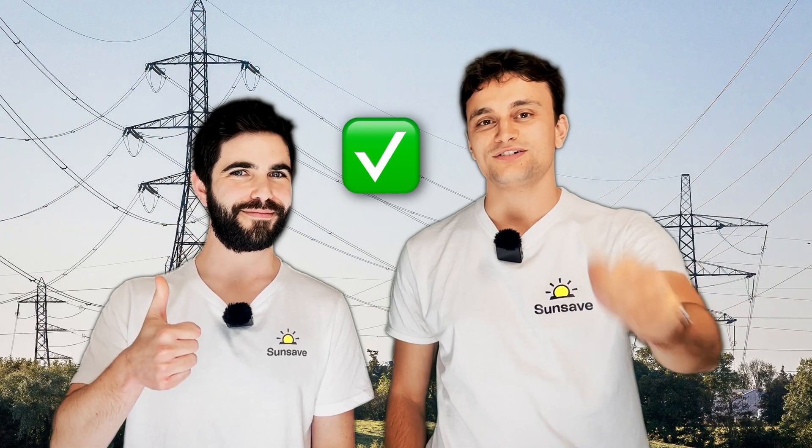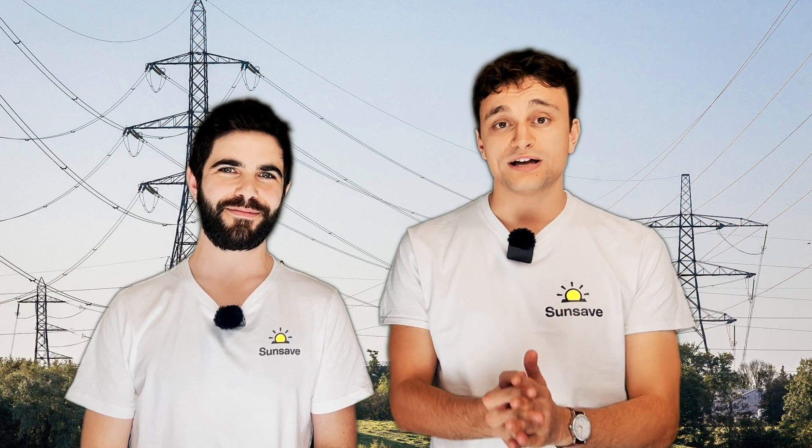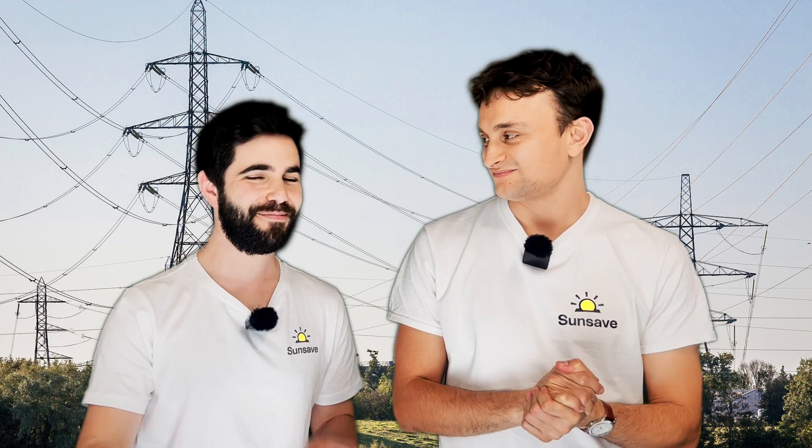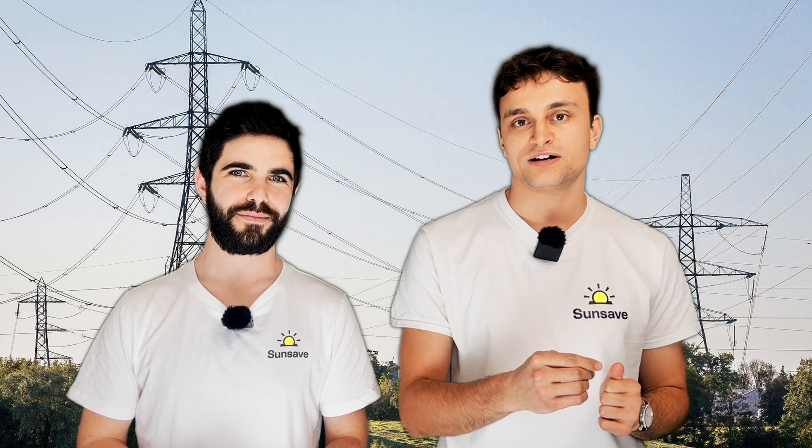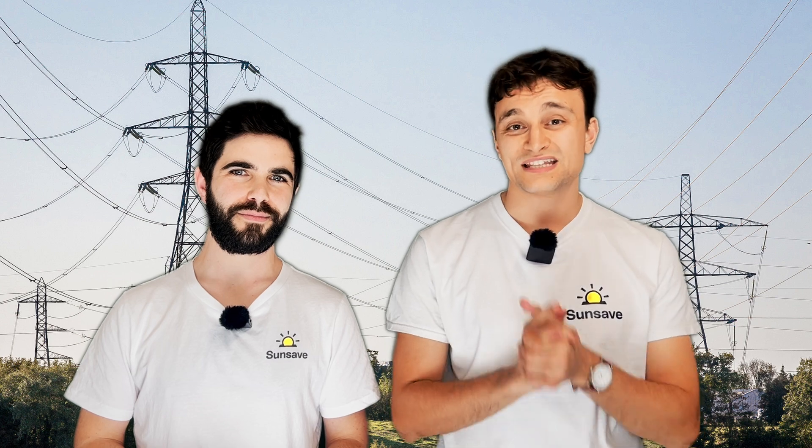If your DNO is happy, it will say yes — crack on. If your DNO is not happy, it will say no, and it will explain the local grid upgrades required. You would have to pay for those, but you can choose whether to go ahead. These changes are usually very expensive and can run into the thousands of pounds. In the vast majority of cases, your application will be approved. All DNOs have to respond to your G99 application within 45 working days. There is also, for some people, a fast-track option known as a Small Generation Installations application, or SGI. If your inverter is between 3.68 kilowatts and 7 kilowatts, and your DNO is signed up to the SGI scheme, they will respond within 10 working days. Once approved, your DNO will send you a unique 13-digit number known as your Export MPAN, which you'll pass on to your energy supplier before you can start receiving export payments.